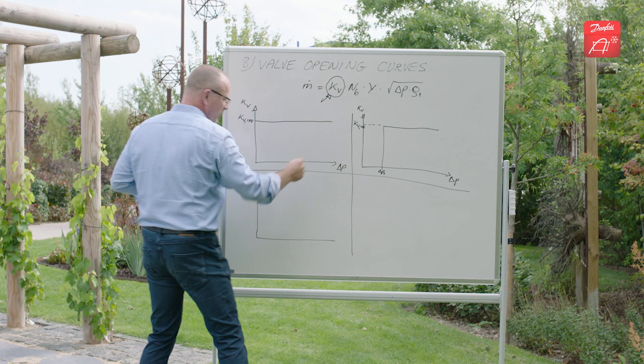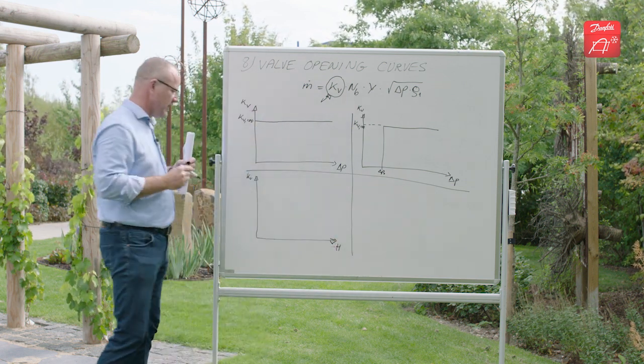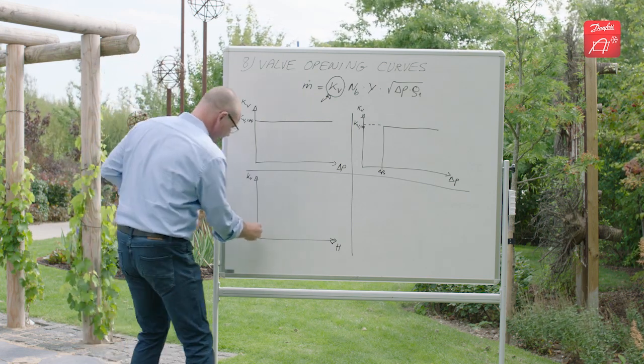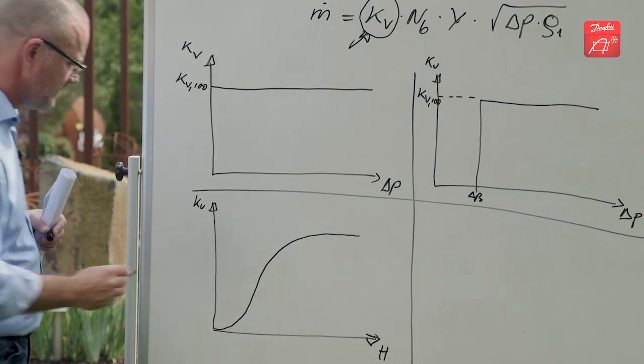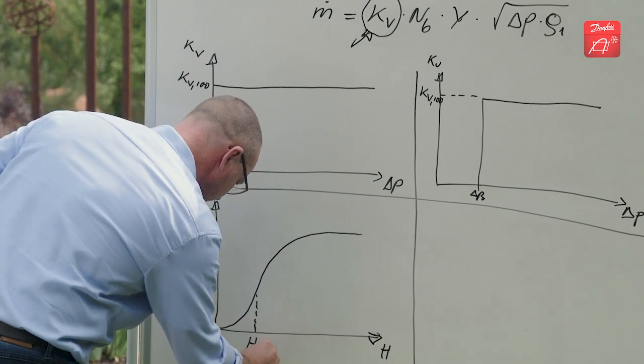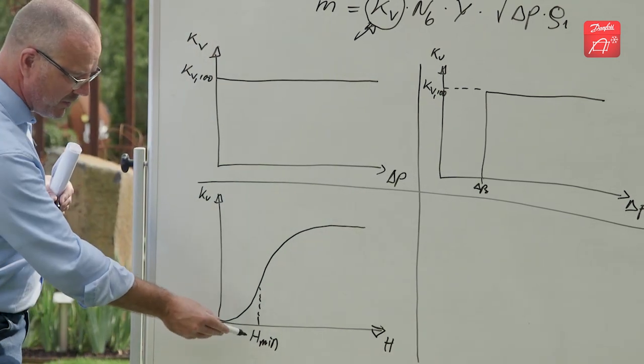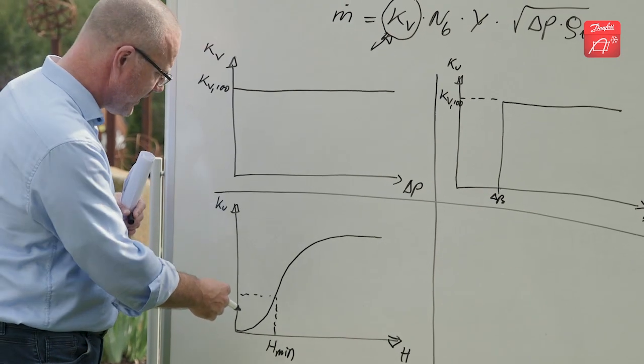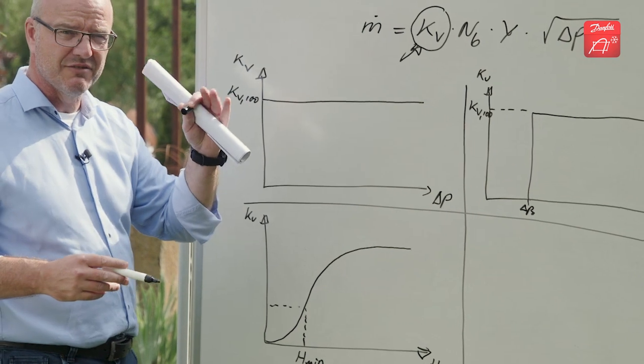So instead of pressure drop across the valve, we will here write the valve travel H. So that is how much the valve is open. The opening characteristic of this valve looks more or less like this. We define a minimum opening below which we don't recommend the valve to be operated. And this is because if you go below the minimum opening, there is a chance of valve fluttering.